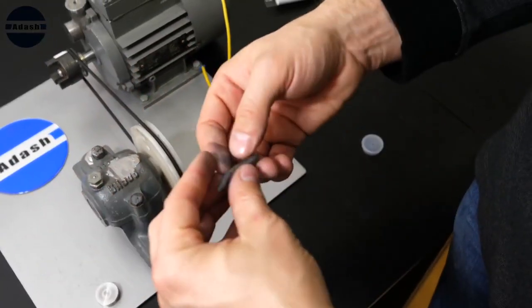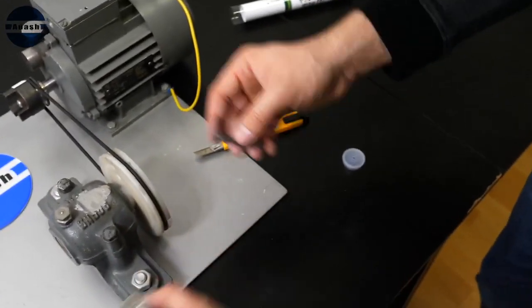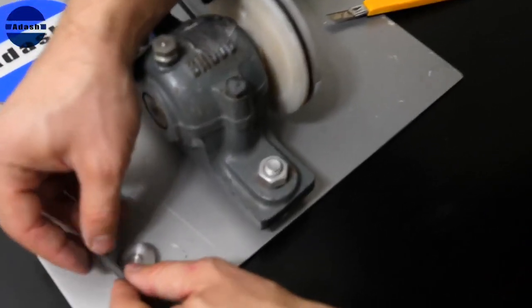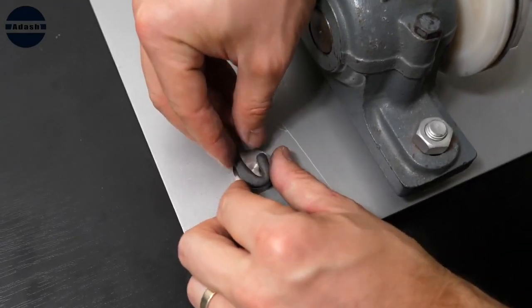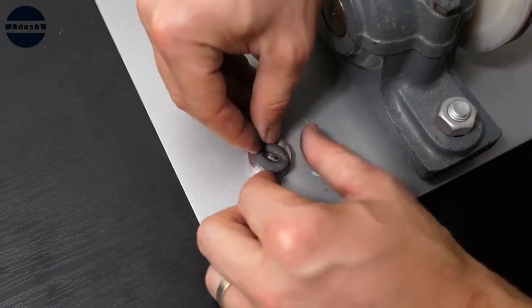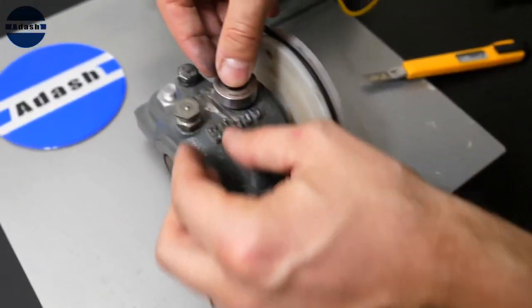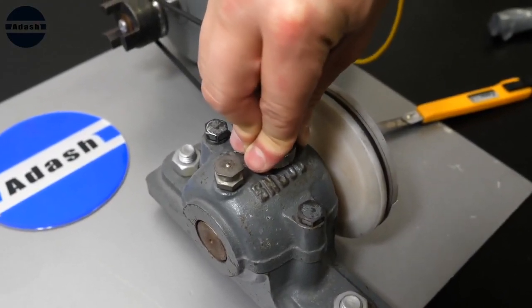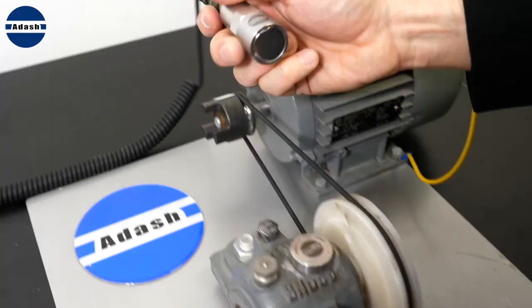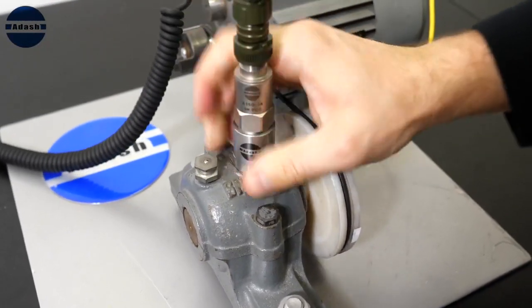The next step is the preparation of measurement points. Good preparation ensures repeatability of measurements. It is key factor for vibration diagnostics. It is critical mainly for bearing condition measurement. The standard way is using of pads. They are glued to the machine and ensure correct signal transmission path to the sensor. The readings are repeatable and this property is very important.